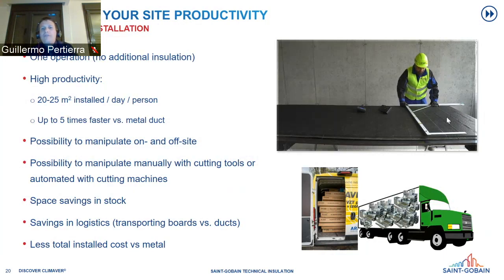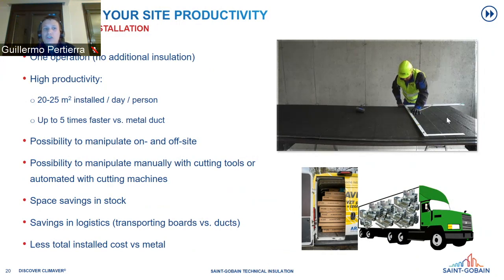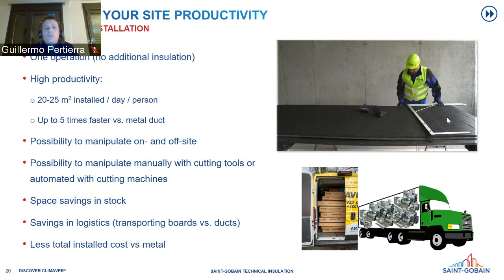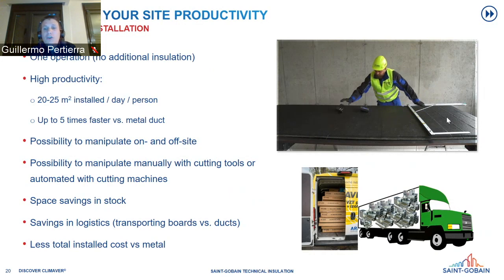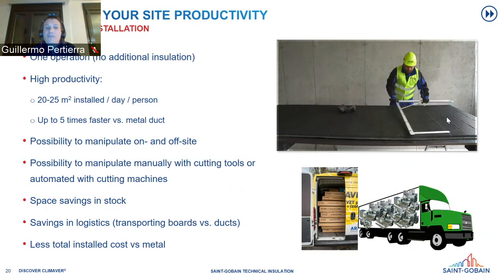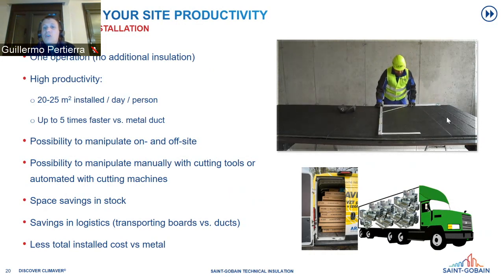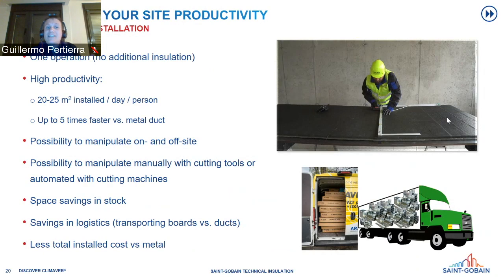You have the duct and the insulation in the same product, so you reduce a lot of the time needed for installation. We can say you'll reduce up to 5 times the time needed compared to installing insulated metal duct. The productivity is between 20 and 25 square meters installed per day per person.